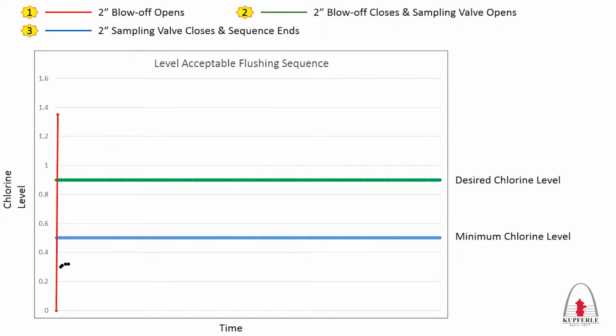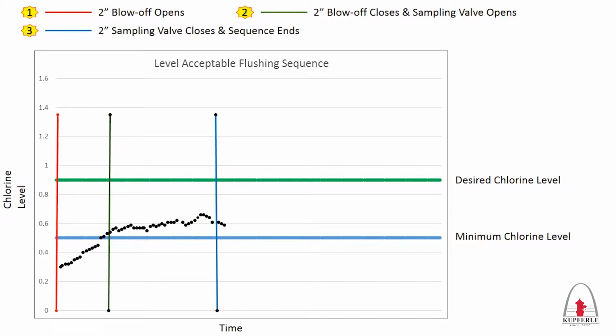If the sampled water's residual level is above the program minimum chlorine level, the unit will continue to sample and check to make sure the residual doesn't drop below the minimum residual level for the sample duration time. As long as the residual level remains above the minimum level, no additional flushing occurs. Initial and final chlorine levels, time of day, and flush duration data is recorded onto the PLC and is transmitted via the RV50 wireless gateway.